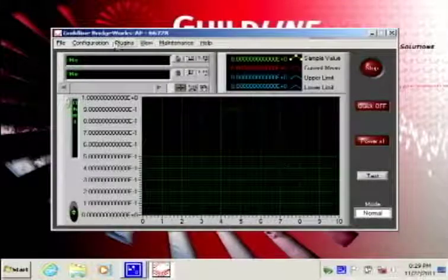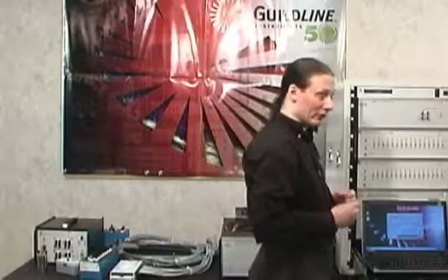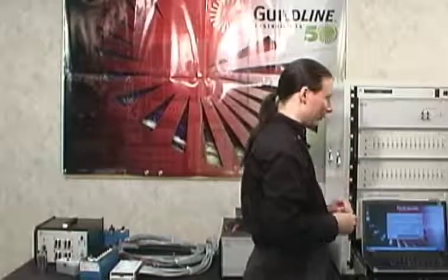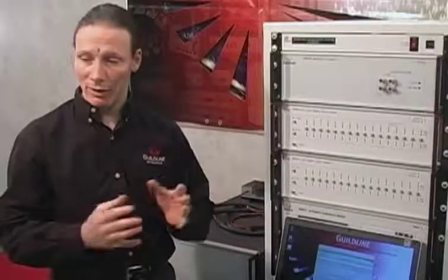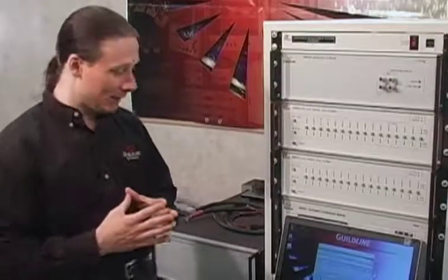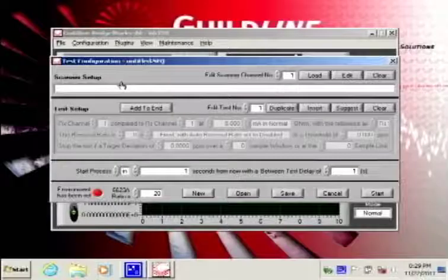And eventually you'll use all these resistor profiles inside a sequence window, allowing you to batch tests and run several tests in automation to save yourself having to sit there and run one thing at a time. You can queue a bunch of tests overnight and let it go, and it'll generate all the results, bring them into a format that you can review, see your data, and generate your reports.